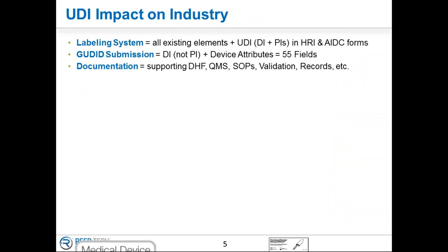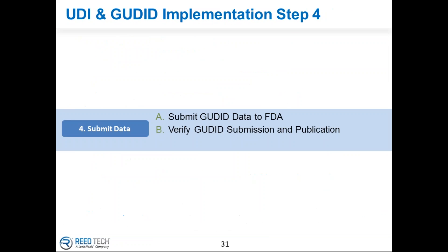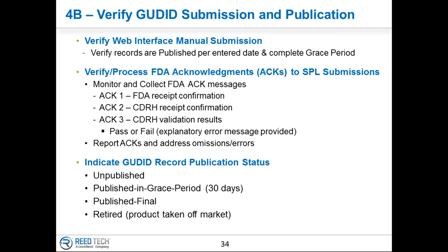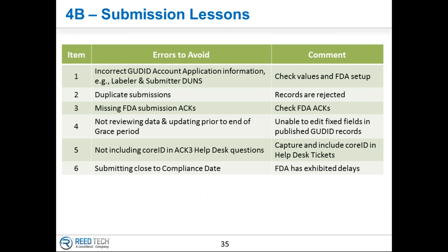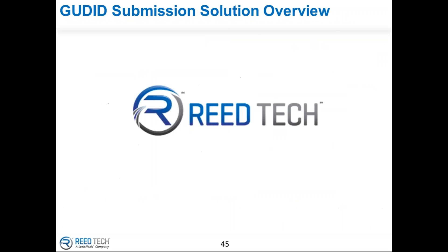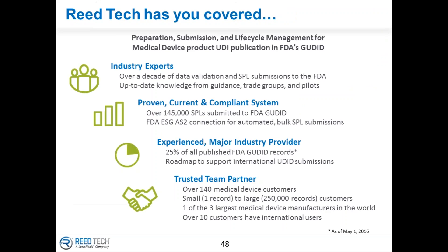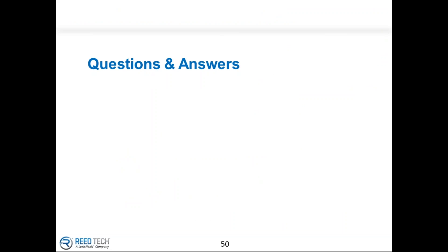Deborah again: if the product is identified with a serial number and that serial number can be internally matched with the manufacturing date, does the manufacturing date also need to appear on the device label? No, it does not. That goes back to the original discussion — if the label did not originally have the date on it, there's no reason to add it. If there's an internal mapping that takes the serial number and returns the date, there's no reason to add that to the label.